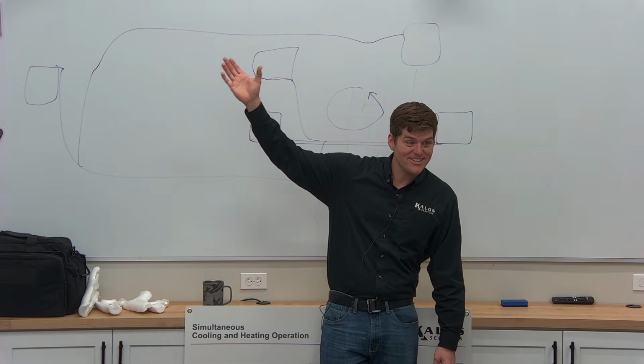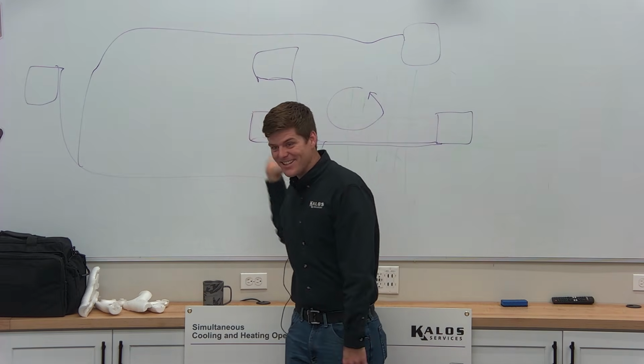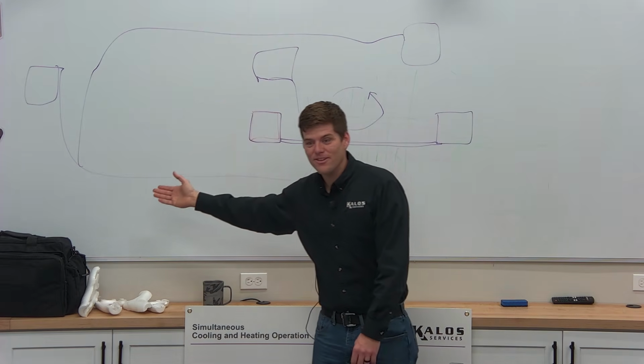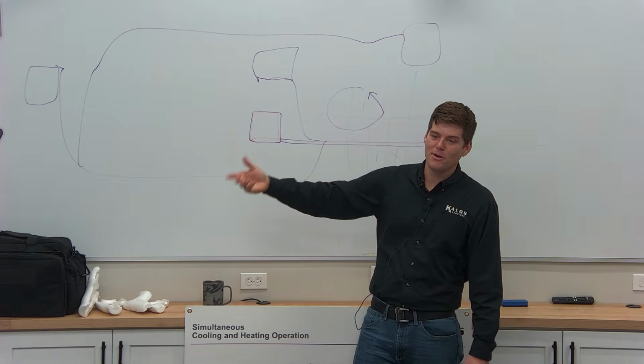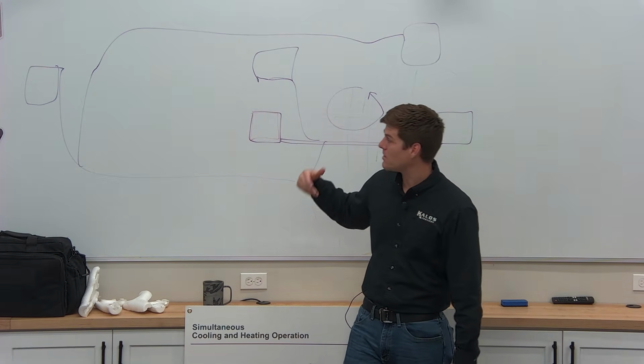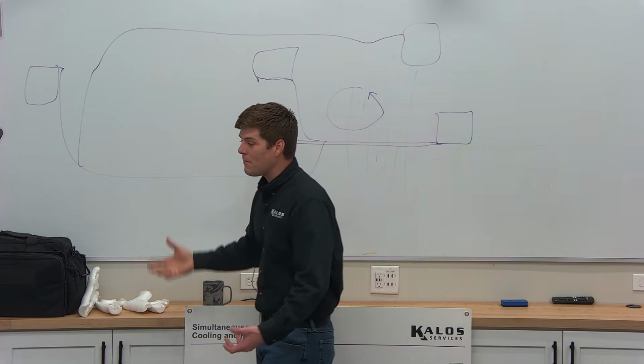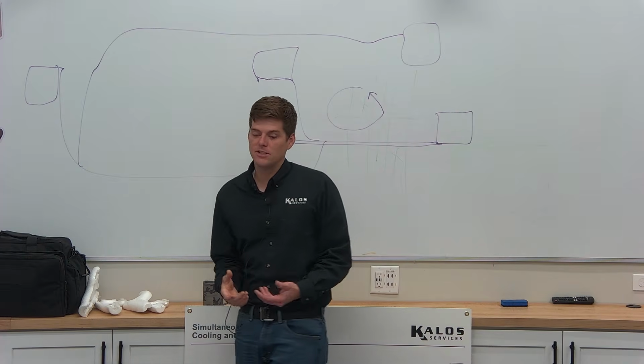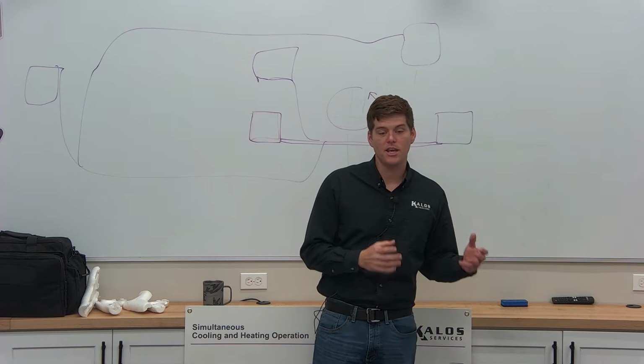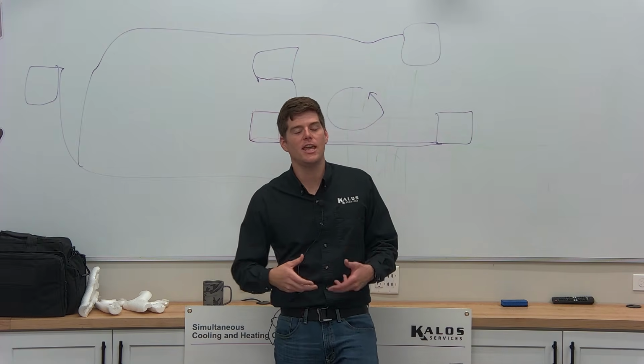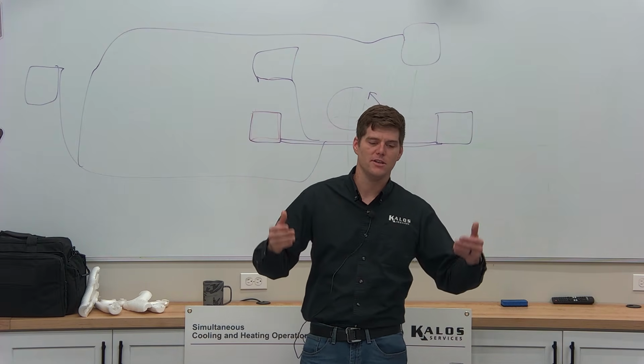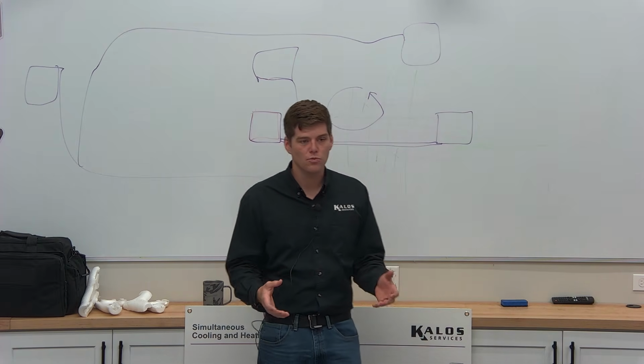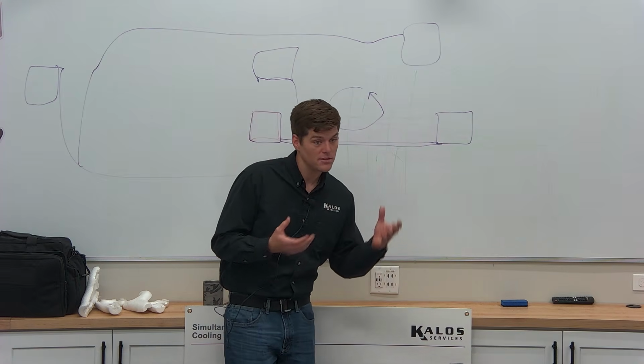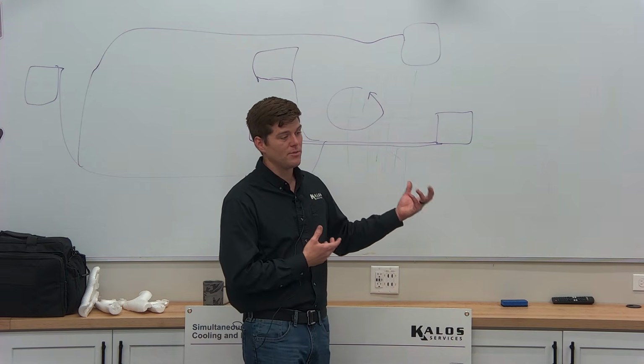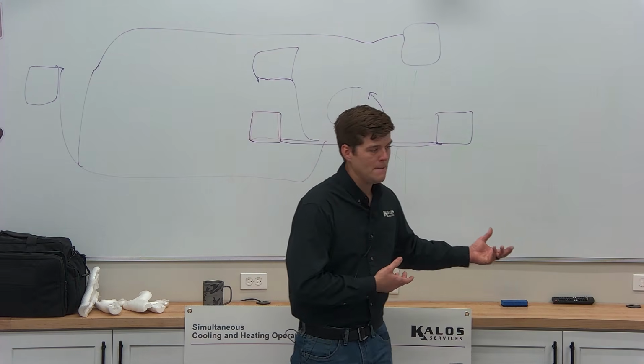This matters because of oil. Compressors come pre-charged with a certain amount of oil. It's still their responsibility, their job. They have parameters. They have safety features that are designed to run the system in a specific way to get that oil back to the outdoor unit. But listen, it can't do everything. It can't overcome physics. It can't overcome gravity. The rules and laws of physics still apply to this particular system. It doesn't live in a separate dimension doing whatever it wants to.